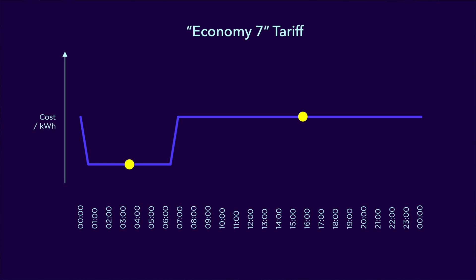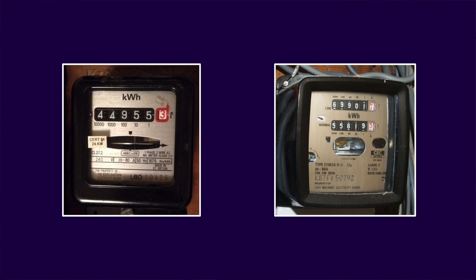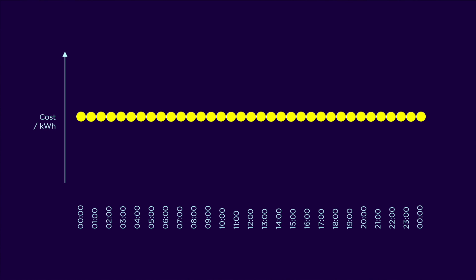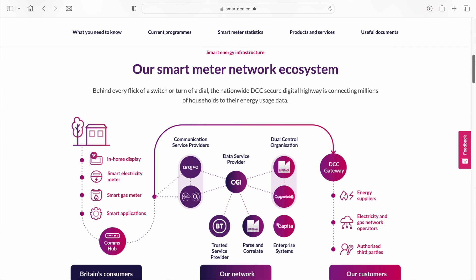The remainder of the day was typically billed at a slightly higher rate than normal. In order to bill customers using this tariff correctly, a special type of meter was required which kept count of the number of kilowatt hours used during the on and off peak periods. The idea was to increase demand during the off-peak period, and this would also reduce the peak period as consumers shifted some of their load to off-peak. This tariff still exists today, although the old analog meters are gradually being replaced with digital smart meters. What's revolutionary about these newer types of meter is that they can keep count of the number of kilowatt hours used every half hour of the day, and then periodically upload this data to a central database. In the UK over 25 million homes are fitted with smart meters today.